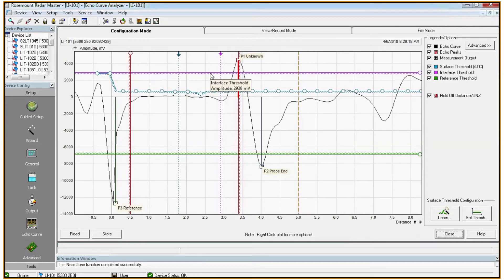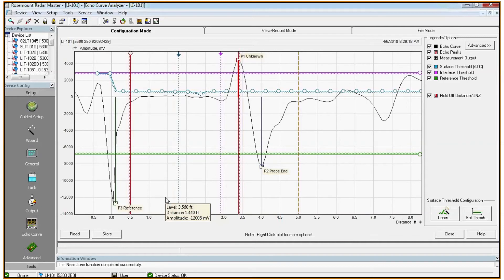Once the learn function is complete, you'll find that your blue and possibly your purple line here will have moved. That's completely normal. It's just adjusting the thresholds to help null out any noise that's in the vessel. Whenever you're able to load an echo curve when the tank is empty, it's always a good idea to save an as-found plot. So if we have any issues in the future, you can send us a copy and we can read through and just see if there's any obstructions or any noise in the tank that needs to be filtered out.